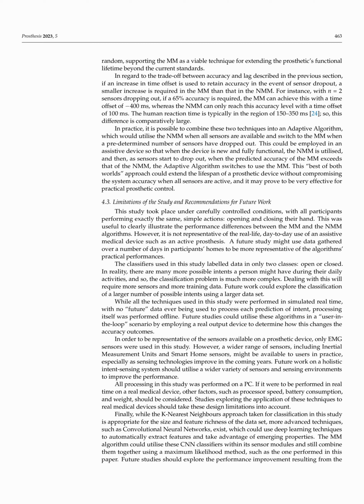In practice, it is possible to combine these two techniques into an adaptive algorithm, which would utilize the NMM when all sensors are available, and switch to the MM when a predetermined number of sensors have dropped out. This could be employed in an assistive device so that when the device is new and fully functional, the NMM is utilized, and then, as sensors start to drop out, when the predicted accuracy of the MM exceeds that of the NMM, the adaptive algorithm switches to use the MM. This best of both worlds approach could extend the lifespan of a prosthetic device without compromising the system accuracy when all sensors are active, and it may prove to be very effective for practical prosthetic control.